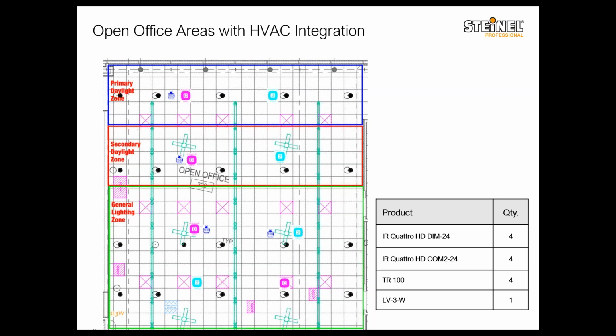So the wiring diagram for this would be a bit too complicated to show and explain here. But as you can see, it's quite complicated, and it's got pretty much everything you can have in a lighting control situation. That can be taken care of with a combination of DIM-24 sensors and COM2-24 sensors, and power packs for the lighting and for the receptacle control as well. I don't see a scenario that would be more complicated than this. So if you run into something like this, or even more basic, get in touch with us. We have the wiring diagrams ready. It's just not very useful to go over in this webinar how to tie a bunch of wires together.